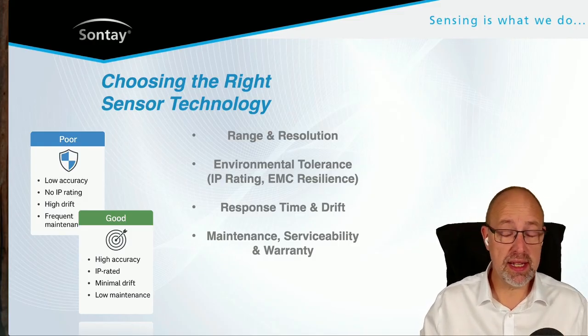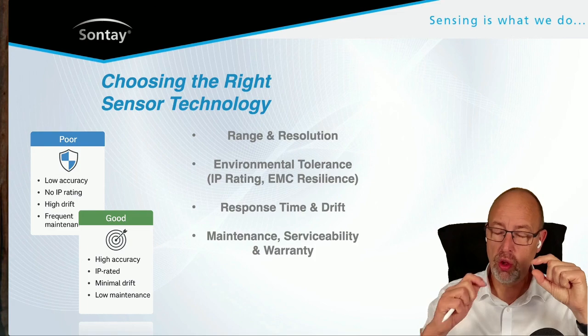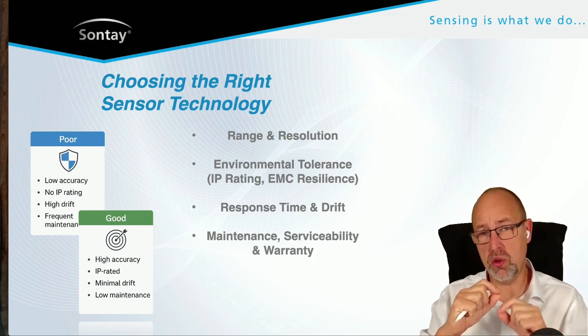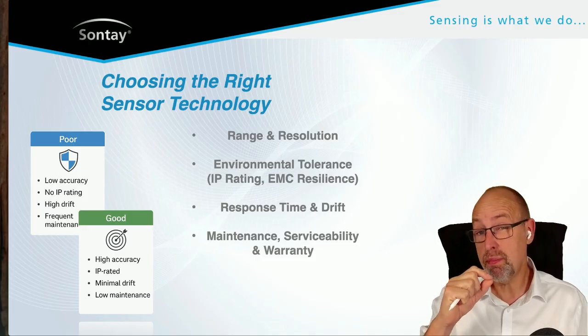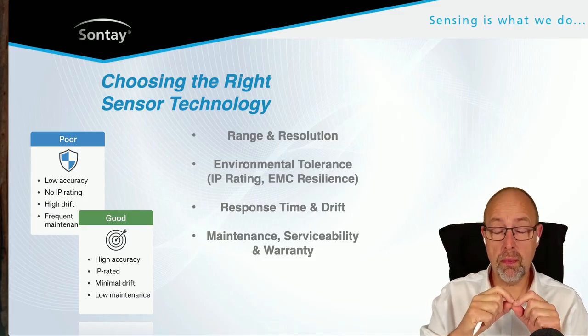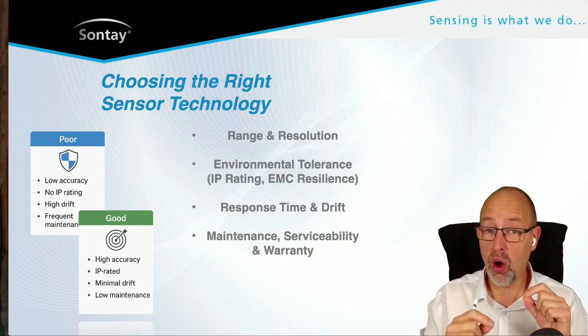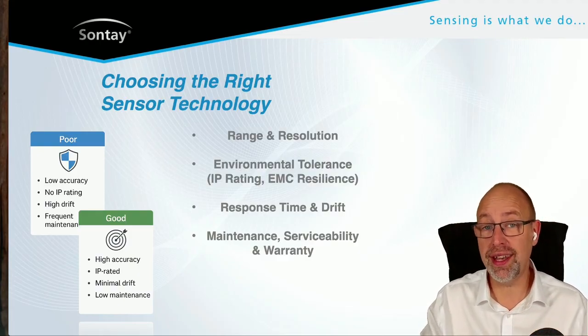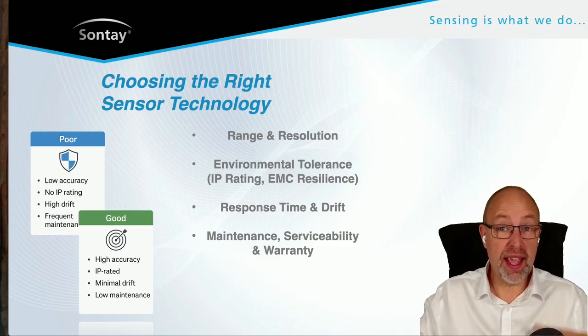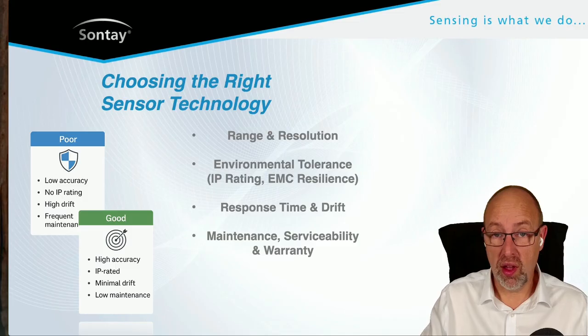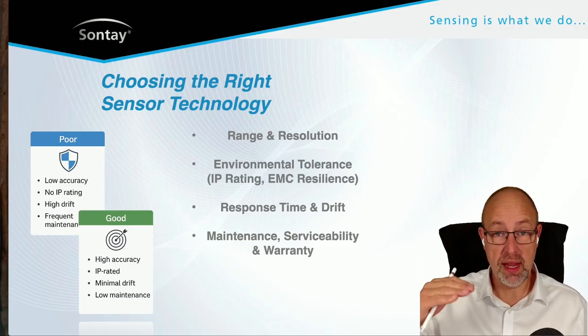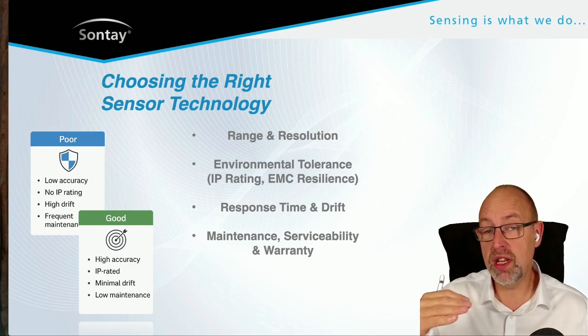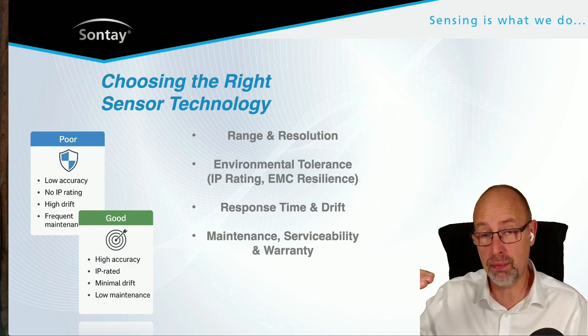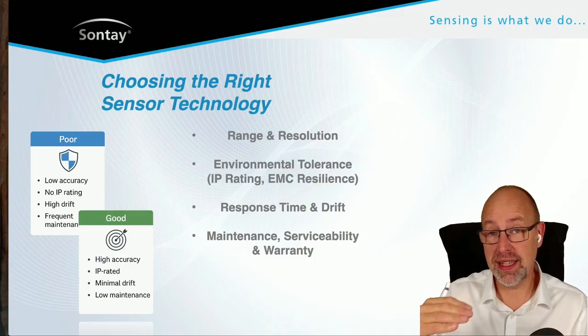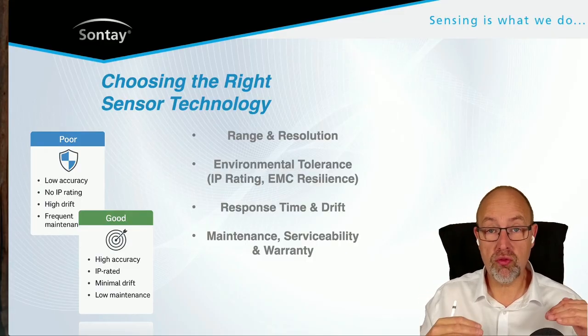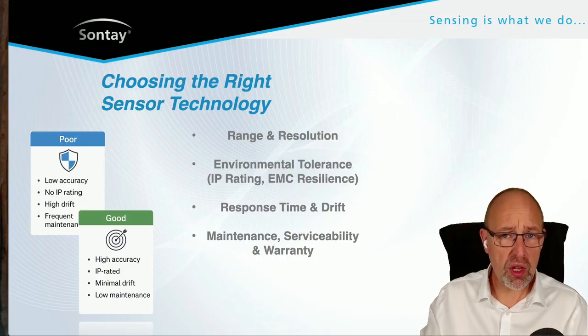If you've got a thermistor sensor, although it's very small, it's not as small as a sensor known as an RTD, which is a resistance temperature detector, which is made out of platinum. And so platinum sensors respond much quicker than thermistor sensors, even though they offer the same accuracy. So if you're looking at dynamic response, say the air conditioning failed in a data hall, the platinum sensor will respond much more quickly to that rise in temperature. Eventually, they'll both get up to the same temperature, but if you need to raise an alarm when you're getting up to a particular temperature, then you're going to want to use the right sensing technology to do that. So choosing the right sensing technology for your response time is very important, depending on your needs.